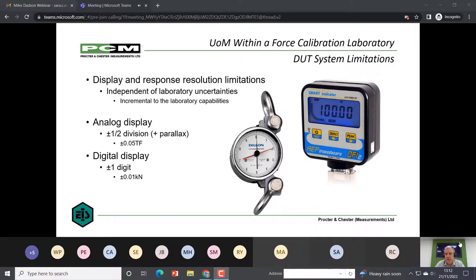And on the right-hand side with the digital display, you've got a resolution of two decimal places. Realistically, that's one part in 10,000. That's going some for an industrial instrument. So you've got those issues associated with uncertainty as well, which is why some calibration certificates will give you an uncertainty of the laboratory's measurement system plus then a digit for the device under test.